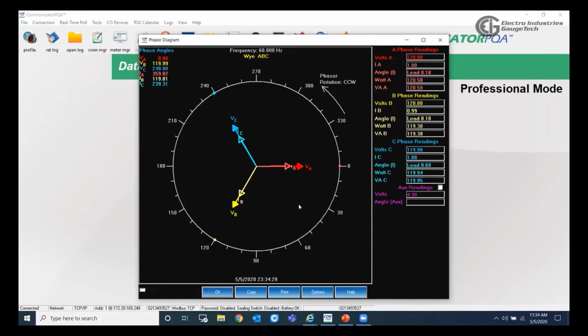This meter is in the lab, and that's why you can see it has a very good power factor, which is 1, and the current and the voltage are in phase. In real life, we would be looking at a small angle between the voltage and the current. But if it's something different than that, then we can determine what's wrong with the wiring, if it's a reverse polarity, if it's across phases, and how to fix that.